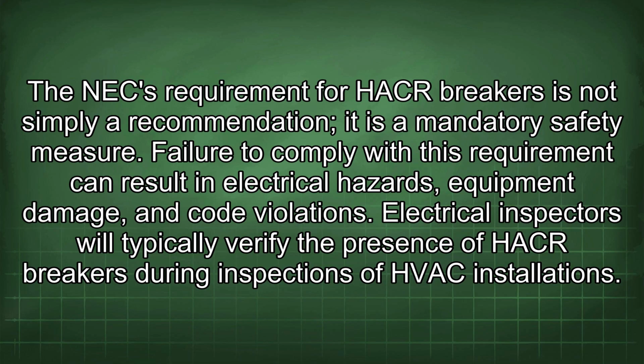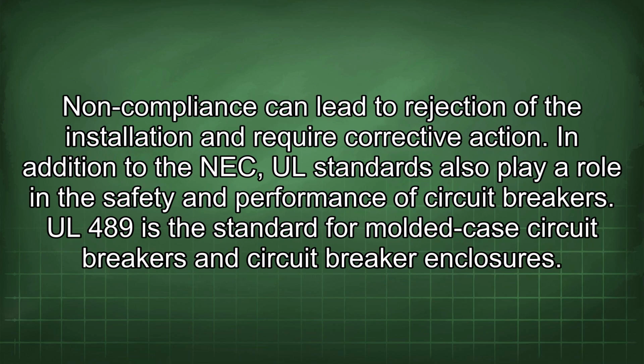The NEC requirement for HACR breakers is not simply a recommendation, it is a mandatory safety measure. Failure to comply with this requirement can result in electrical hazards, equipment damage, and code violations. Electrical inspectors will typically verify the presence of HACR breakers during inspections of HVAC installations. Non-compliance can lead to rejection of the installation and require corrective action.